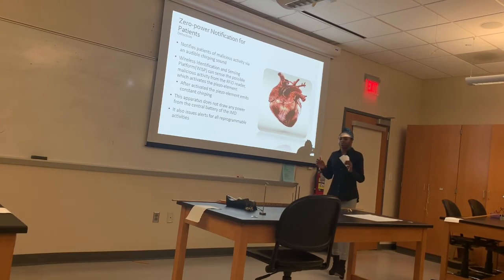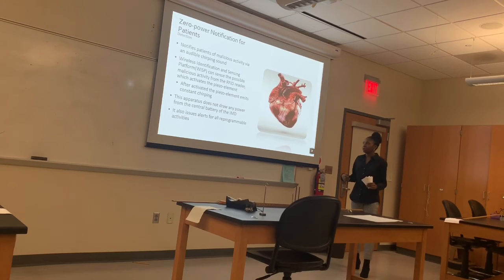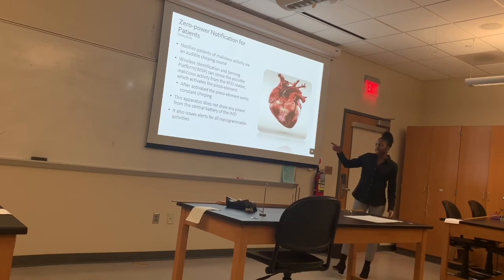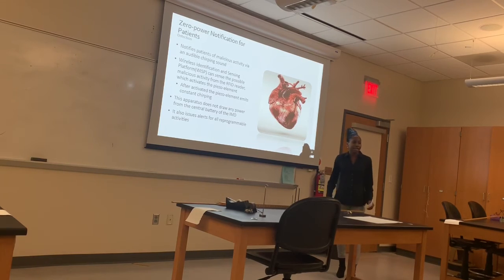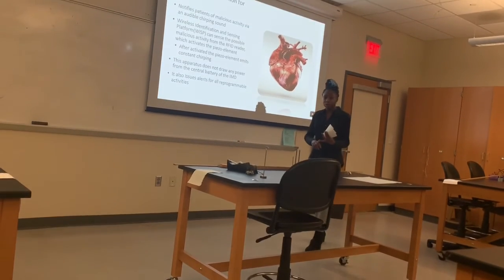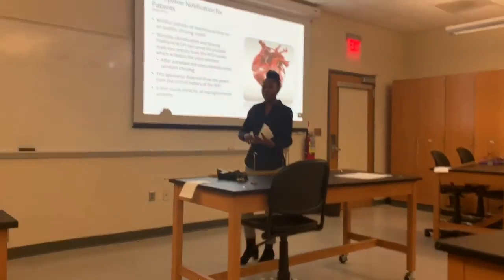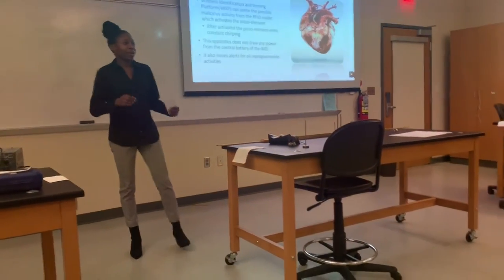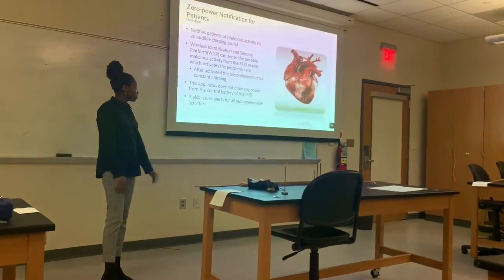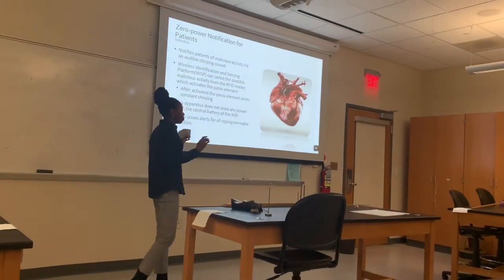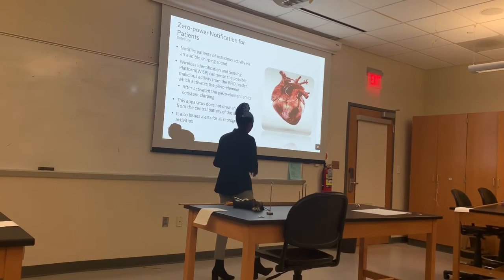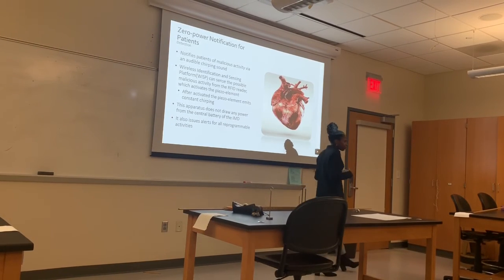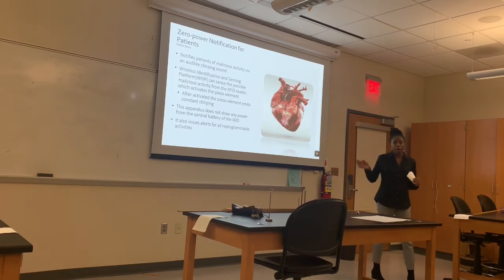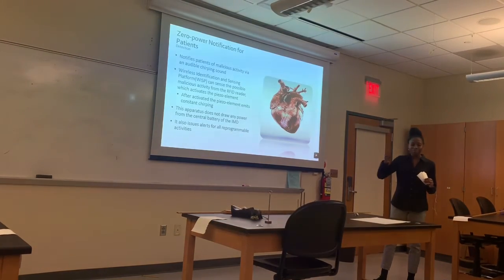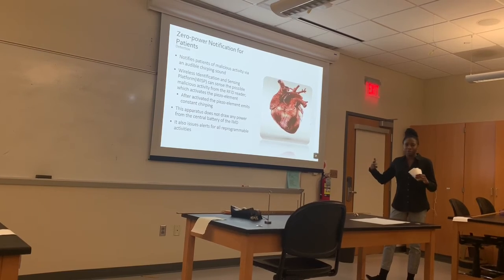So our first security measure is a detection security measure. They are suggesting that the IMD be equipped with a wireless identification and sensing platform, in which if it senses that either a commercial programmer or an unauthorized programmer is attempting to alter therapies, a piezo element will then be triggered and the patient will then hear a loud chirping sound. Now, this is a plausible security measure because it does not draw upon the IMD's main battery source, but one thing to note is that it's going to chirp if it's a commercial programmer or an unauthorized programmer.